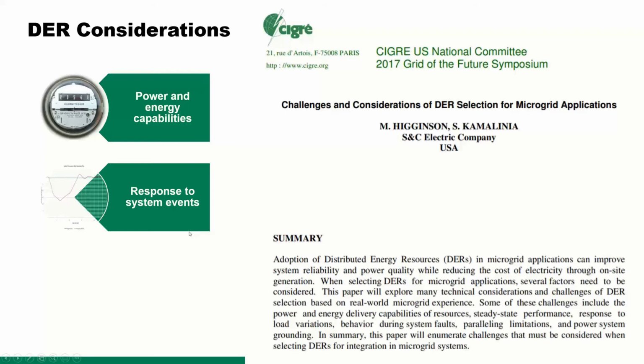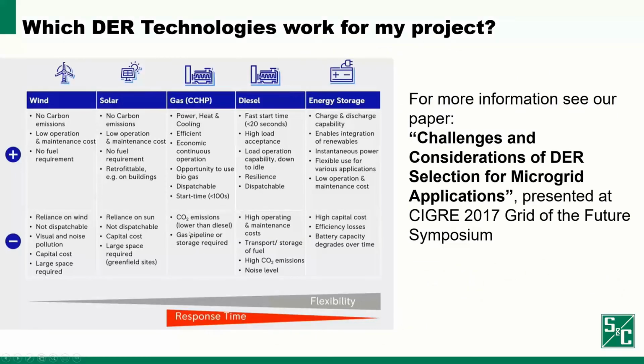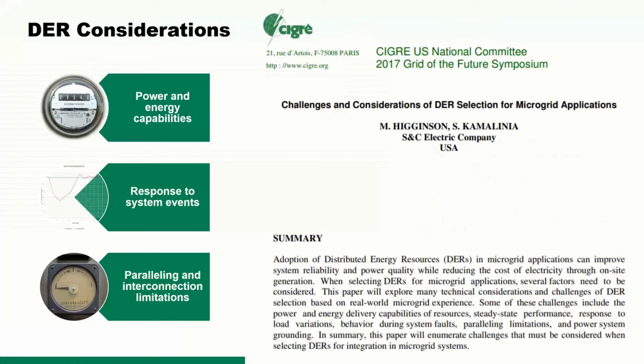So anyhow, these are the three main considerations that we want to look for when we are selecting DERs for the system. The first one is power and energy capabilities. Some DERs may have large power capacities, but may not necessarily be able to put that power out very quickly. In a reverse situation, a DER may have a large energy content, but not a lot of power capacity. And the second feature is the response time to the system event. By system event, I mean any change in the current state of operation in the system, like changing the load or occurrence of a fault. For example, inverter-based sources have significantly faster response time since they do not have the inertia that the reciprocating machines have.